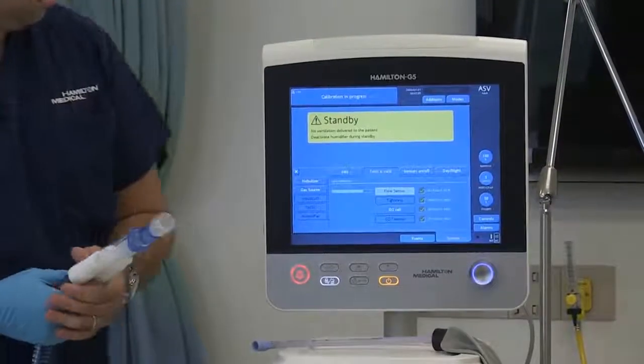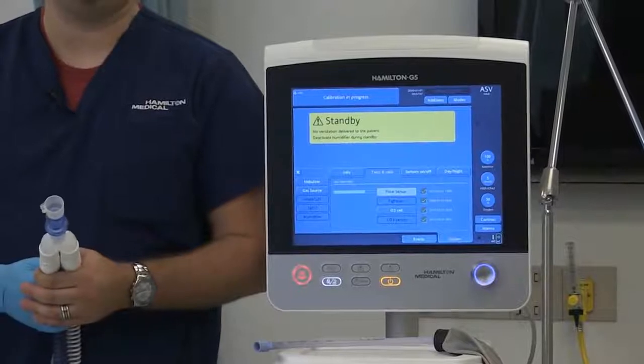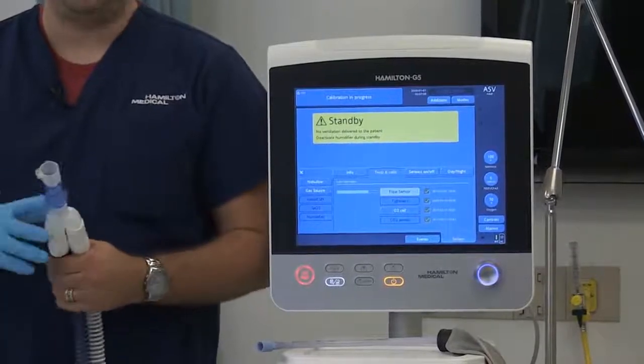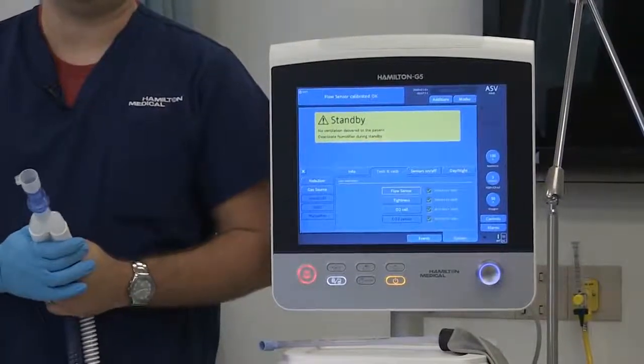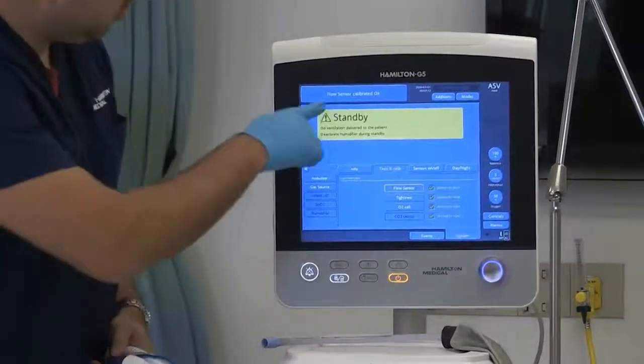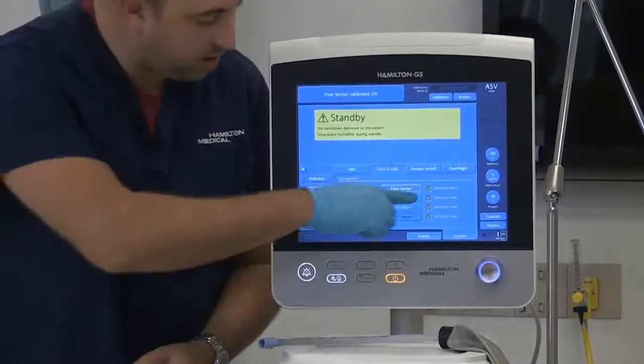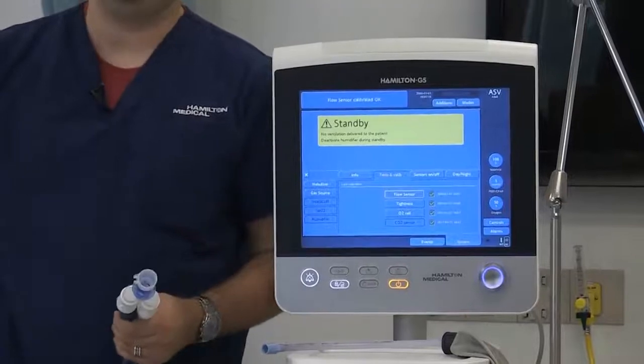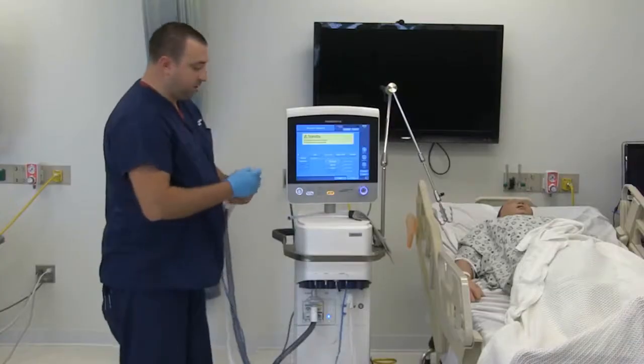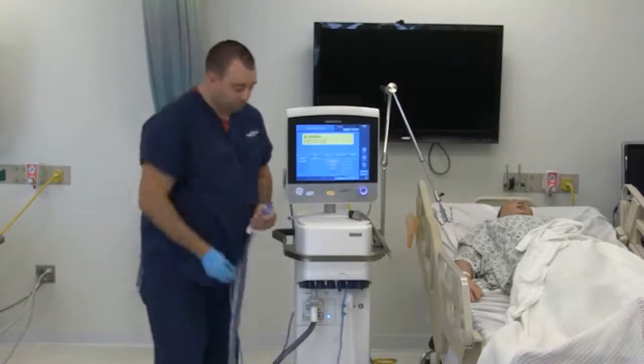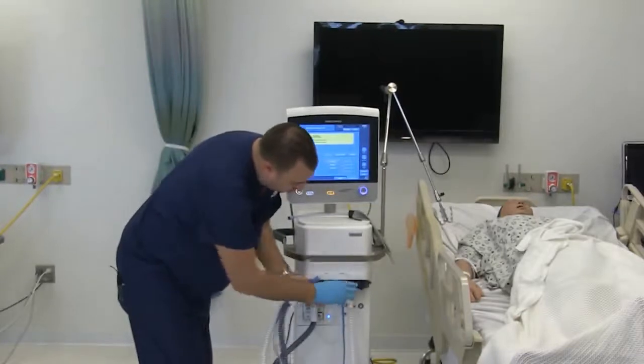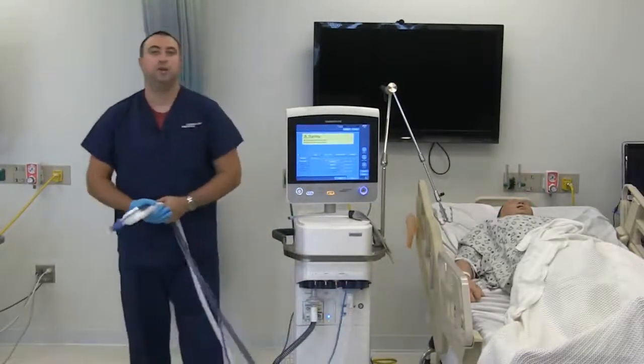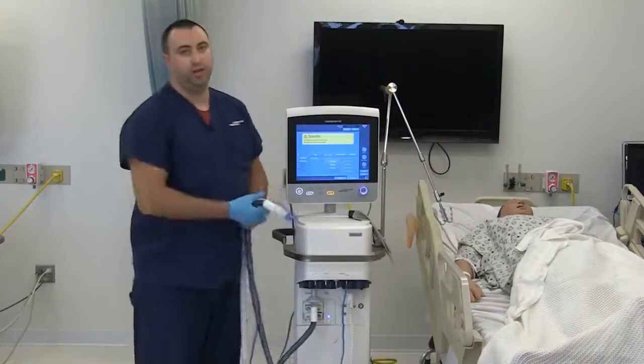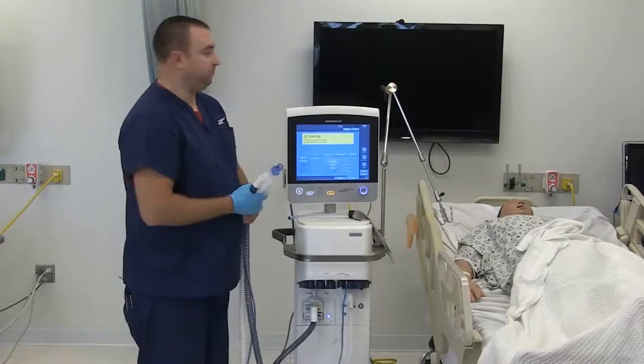Once your flow sensor and your tightness test are complete, you are ready to place the ventilator on a patient. Flow sensor calibrated okay. We have a green check mark. You are good to go. This piece comes with a clip, so you can clip it onto your flow sensor tubing so that you will have it for future needs of flow sensor calibration.